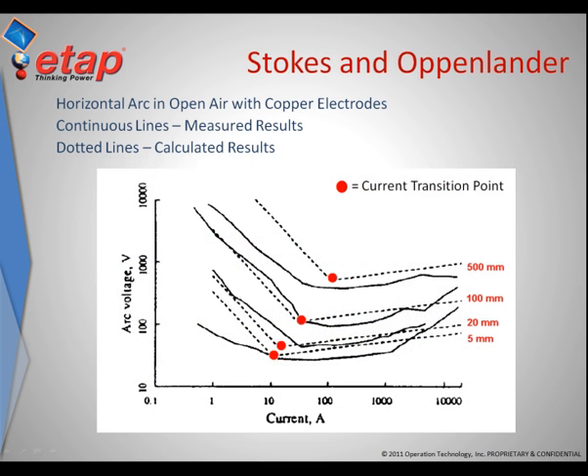This is important because we will now have a more realistic representation of the arc fault current. As can be seen in this slide, we see different test results for different arc gaps. The equations are able to provide results that are coherent with the test results for different arc voltages.